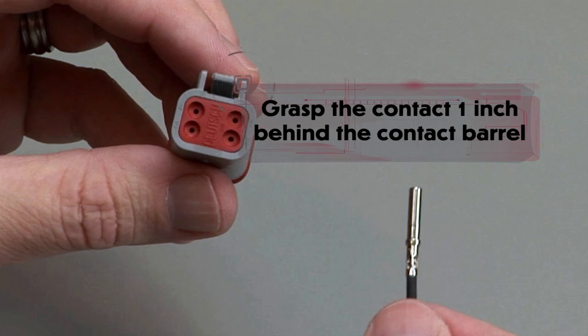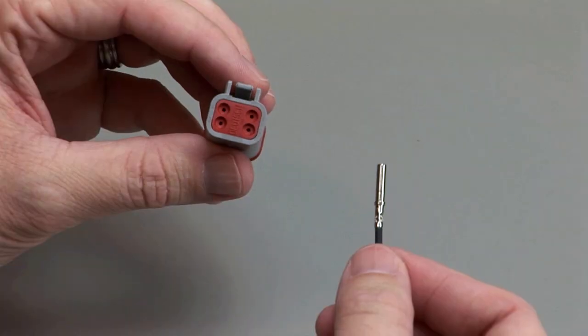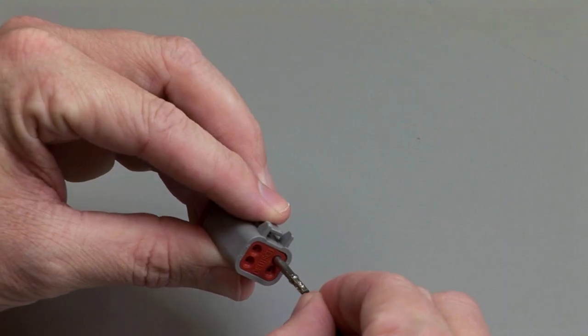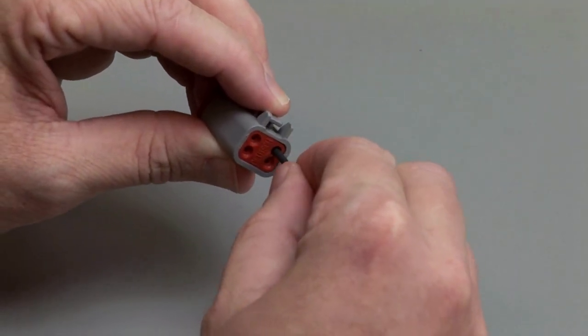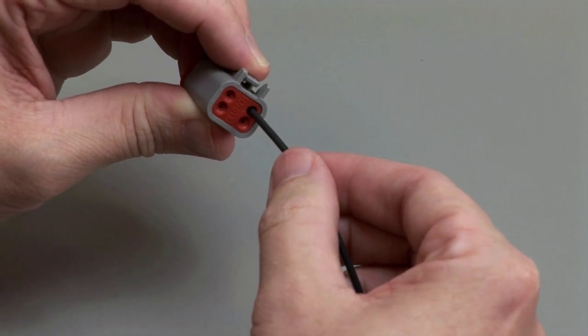Hold the connector with the rear grommet facing you. Push the contact straight into the rear grommet until you hear and feel a click. A slight tug will confirm that the contact is properly locked into place.